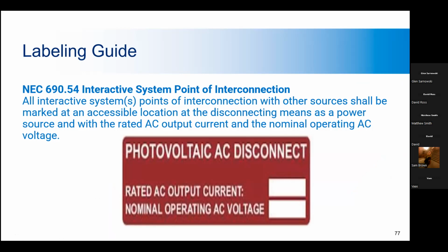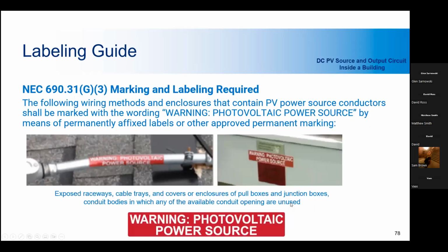And so next we have for inverters, anytime you have an inverter output, that's known as an interactive system point of interconnection. And you have to label with the rated AC output current and the nominal operating voltage. One thing to keep in mind is NYSERDA does not allow writing on these labels. Engraving or printing on it is better, as the writing will fade and basically disappear by the end of the system life. 25 years from now, you would not be able to even see a written value. So you would need to engrave it or have it printed on the label.